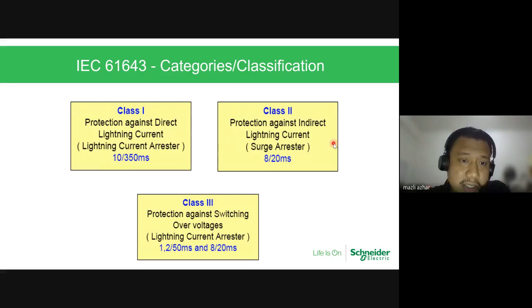For class 1, for direct lightning current or lightning strike. Class 2 against indirect. And then class 3, again, switching over voltage or for sensitive equipment. But commonly people will install class 1 and class 2 at the distribution box. Okay. So when I say direct lightning current, basically you have a lightning rod.